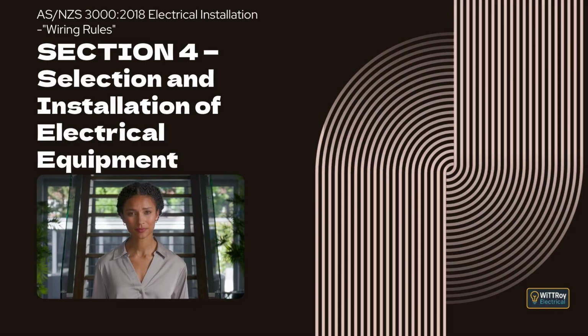Clause 4.5.2.3.4 Classifications of recessed luminaires. This clause explains that recessed luminaires are classified according to recognized classifications that define whether they can be abutted against or covered by normally flammable materials or insulation. It explains the meaning of different classifications and how they relate to access of insulation or debris to heated parts of the luminaire, and it explains that certain classifications are not permitted in residential installations in New Zealand.